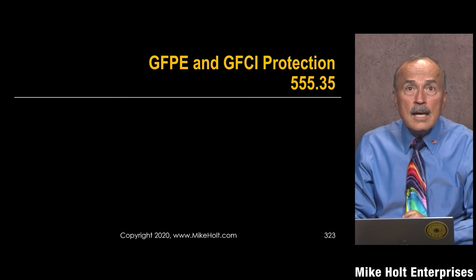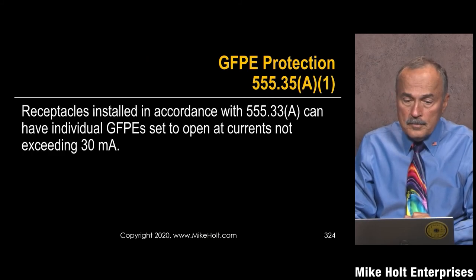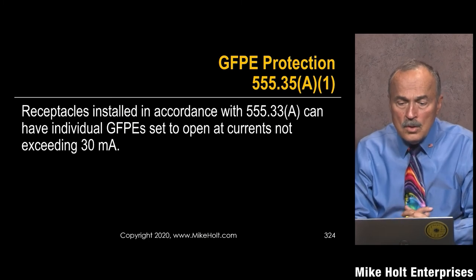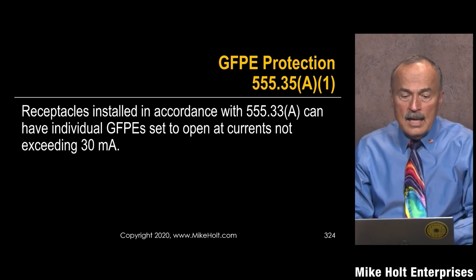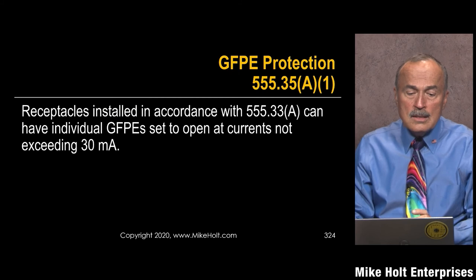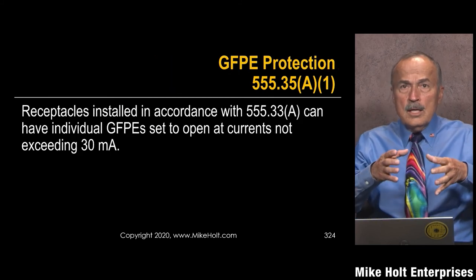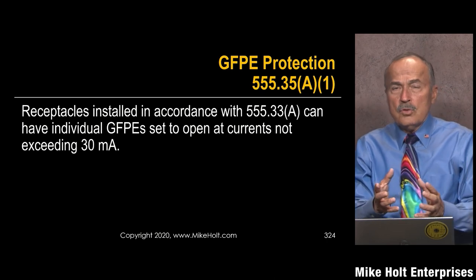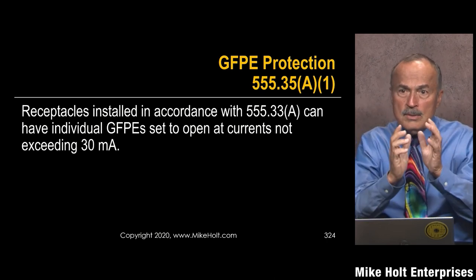GFPE and GFCI protection receptacles installed in accordance with 555.33(A) — the shore power outlets can have individual ground fault protection set to open at currents not more than 30 milliamperes. I'd like to get a picture of a shore power outlet. You have a breaker, and I need to get a picture of a breaker and a receptacle.